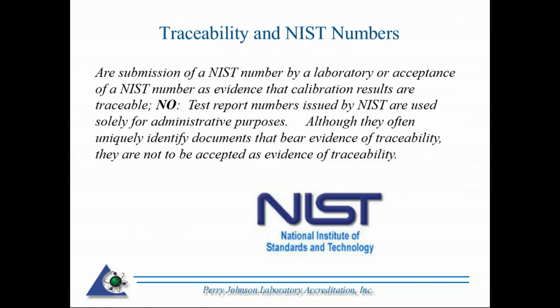Something else I want to highlight here is NIST numbers. You don't see them nowhere near as often as when I first got involved in calibration. NIST numbers on the report. I'll propose a question here. Are submissions of NIST numbers acceptable as evidence of traceability? The answer is no. Why? Test reports issued by NIST are solely for administrative purposes. Although they're often uniquely identified documents that bear evidence of traceability, they are not accepted as evidence of traceability.